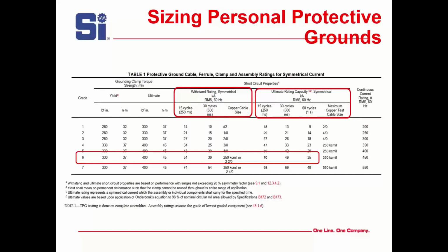So then we slide over to the NFPA, ASTM F855 Table 1. And you notice I have two ratings. The withstand rating is the rating I want to choose. Because if I choose the withstand rating and the ground sees one shot of rated short circuit current, it can take another shot. If I go over to ultimate capacity, and I've seen people do this.